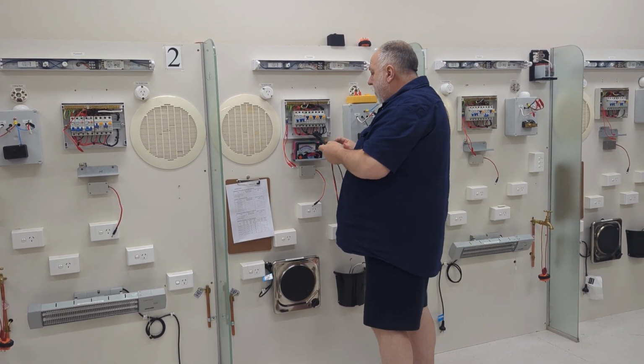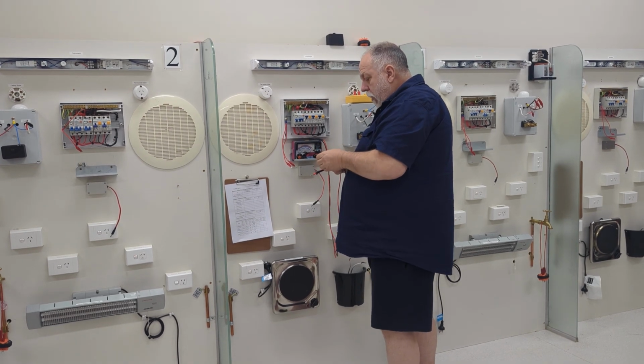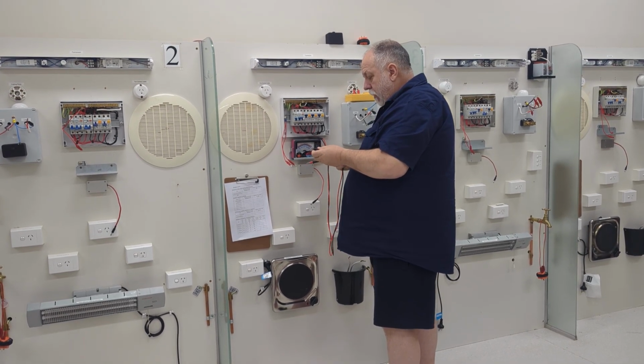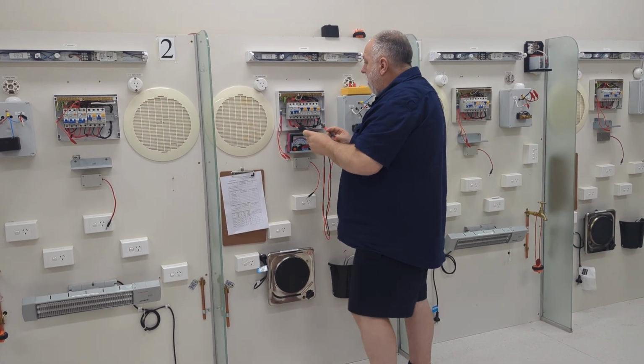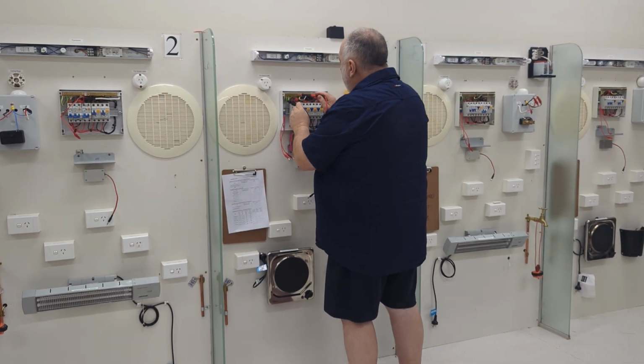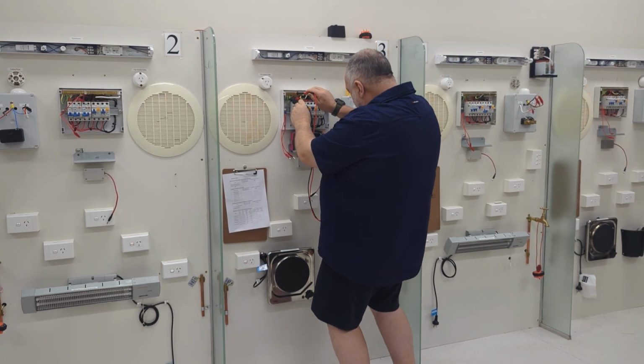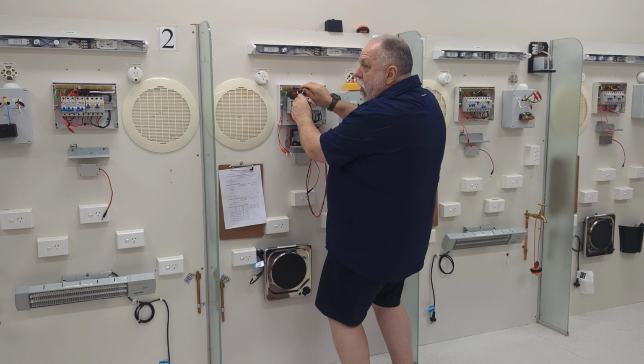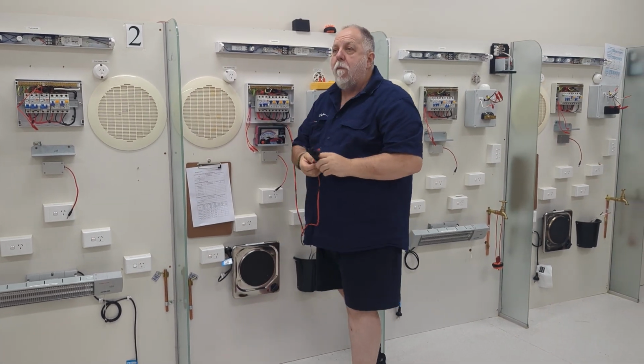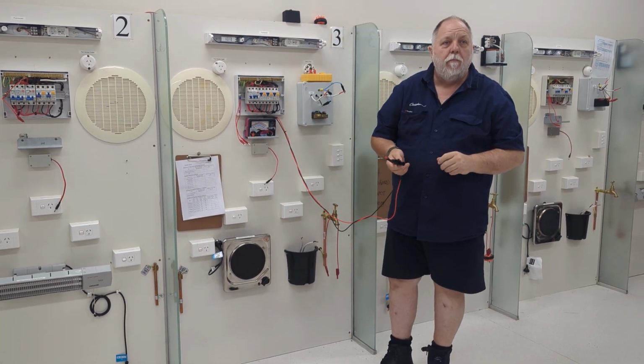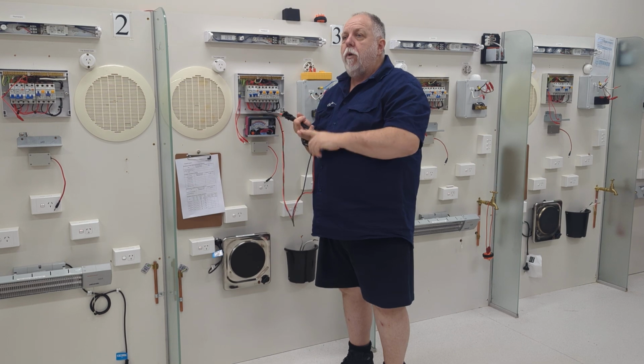Okay, got it on 500 volts, all right? I took the wrong one out, put this on. I'm now going to go between the top of the main switch to my earth, and I've come down to 0.5. Is that a pass or fail? Sorry? Fail. Yep. Minimum reading is 1 meg.